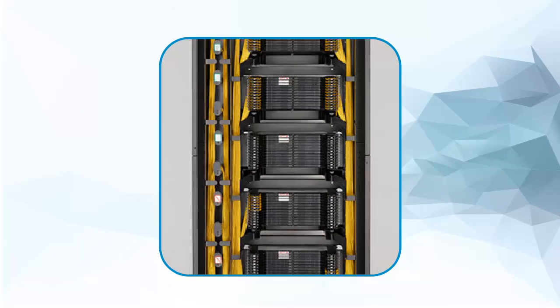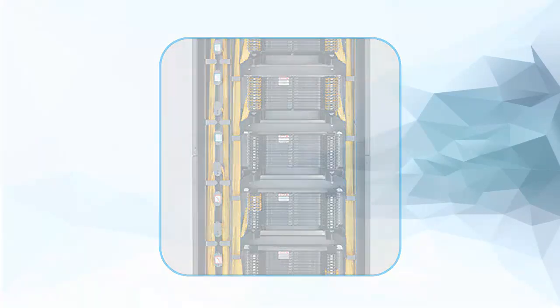Additionally, having proper slack storage for the cross-connect patch cord will ensure that the network can be quickly reconfigured without inducing attenuation on adjacent fibers. An ODF system with a strong, flexible slack storage system will require keeping only a few standard-length patch cords in stock for use in cross-connect routings rather than multiple different lengths.